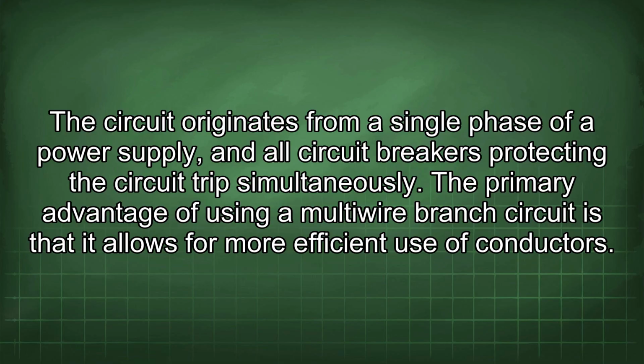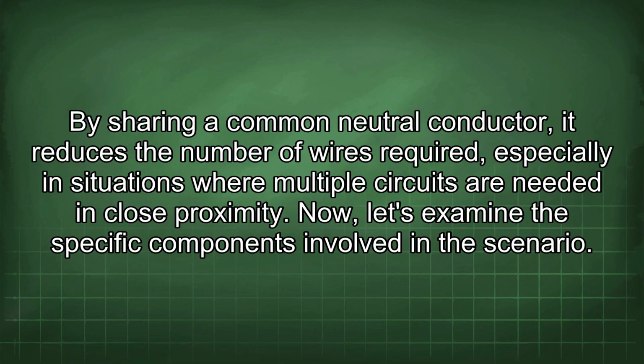The primary advantage of using a multiwire branch circuit is that it allows for more efficient use of conductors. By sharing a common neutral conductor, it reduces the number of wires required, especially in situations where multiple circuits are needed in close proximity. Now, let's examine the specific components involved in the scenario.